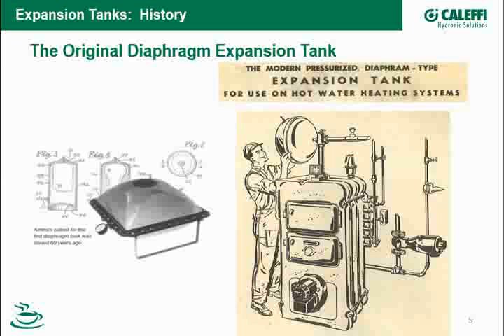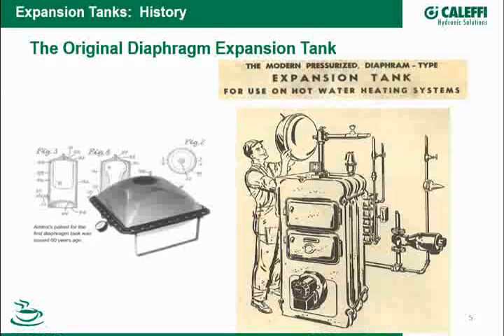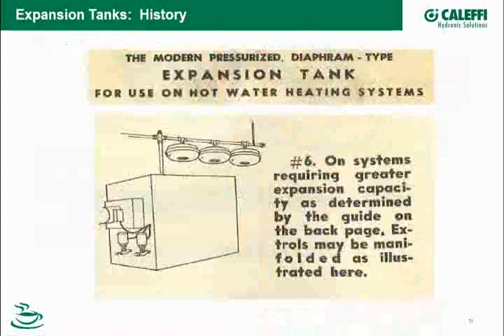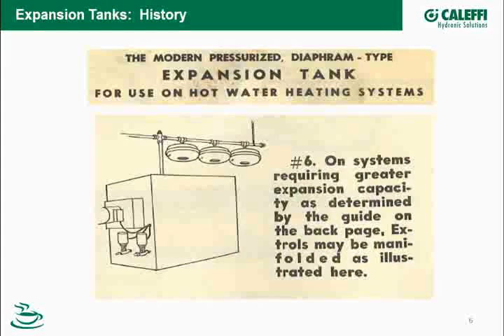The picture on the right is actually out of an Amtrol installation manual from the 60s. So this whole concept of putting the expansion tank in, taking care of the system, has been around for a long period of time. Interesting about the 60s, there wasn't a lot of selection and a lot of sizing. When I look at this, this is showing the gentleman there putting up the expansion tank as they said through the manual. With a larger system, it wasn't about sizing the expansion tank. It was how many expansion tanks did I need to put in that system to take care of the expansion. We've grown quite a bit as an industry since then.